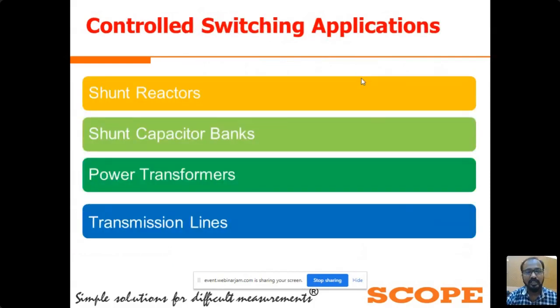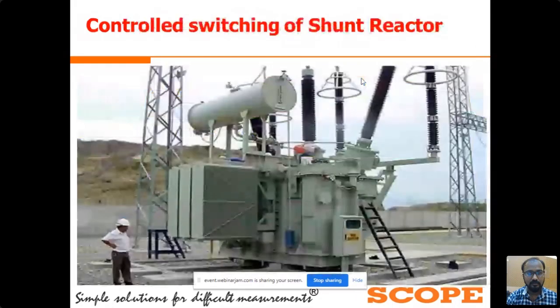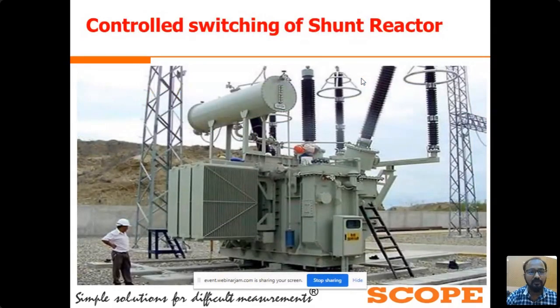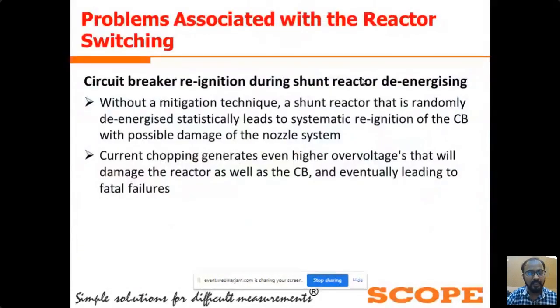Basically, we use the control switching device for the shunt reactor application, shunt capacitor bank application, power transformer application, and the transmission line application. Now we will see the application of the control switching device for shunt reactors. The main problem associated with shunt reactor switching is reignition at the time of de-energization. We have observed that during random opening of a shunt reactor, there is a reignition of current between the circuit breaker contacts.